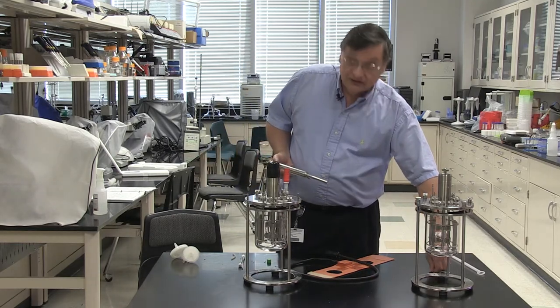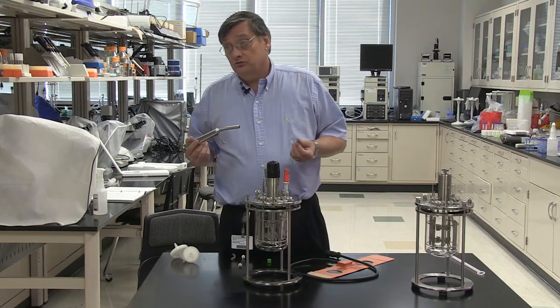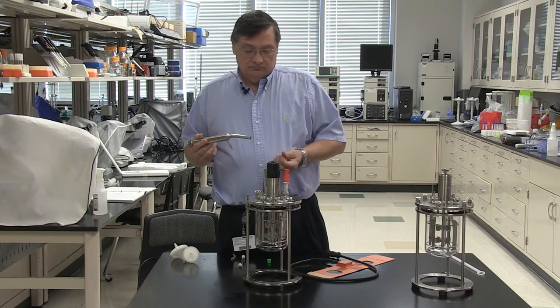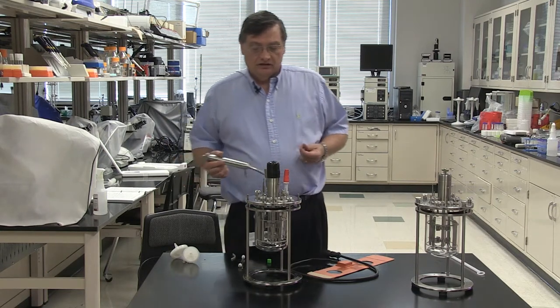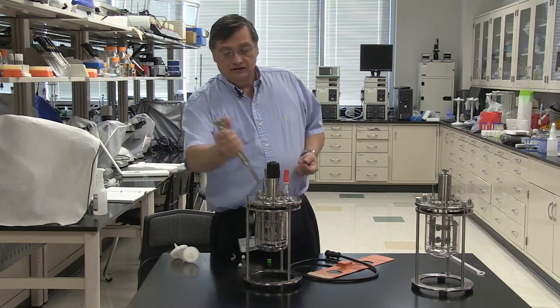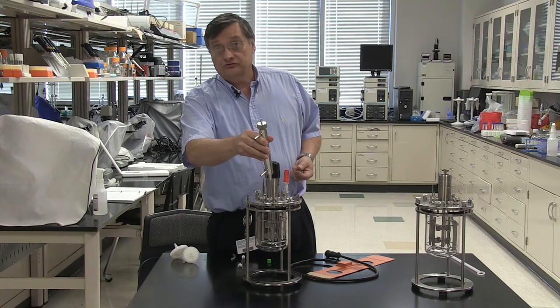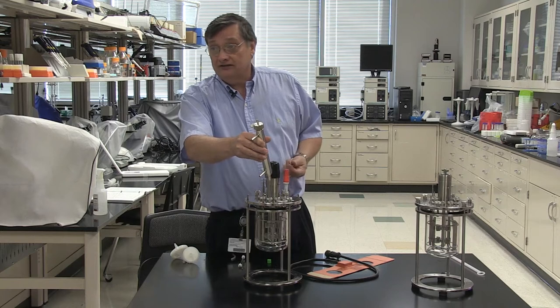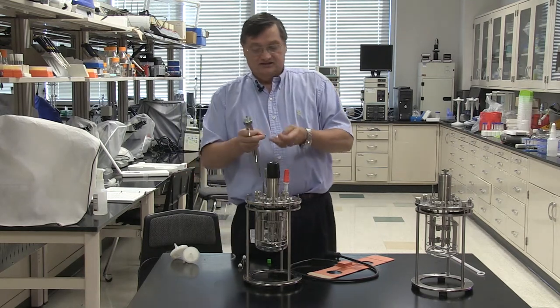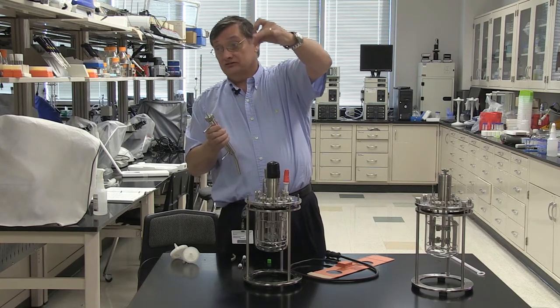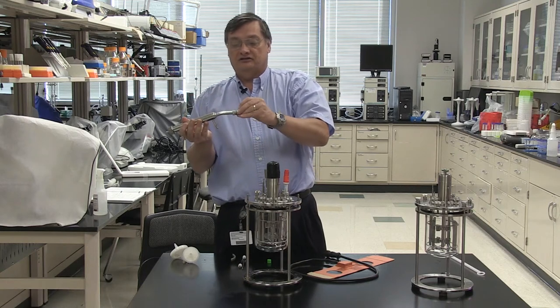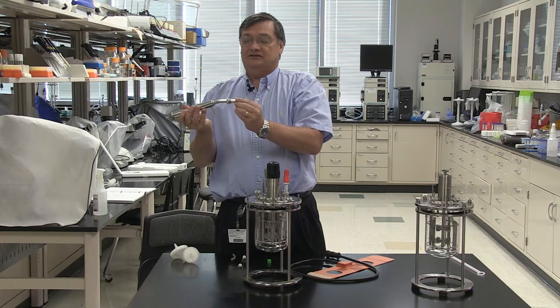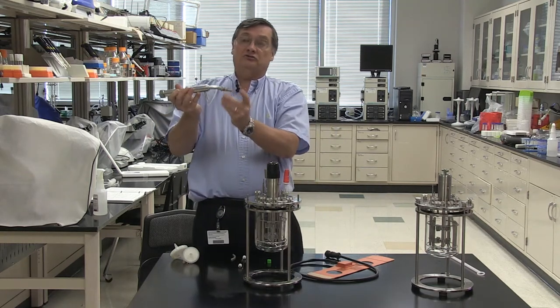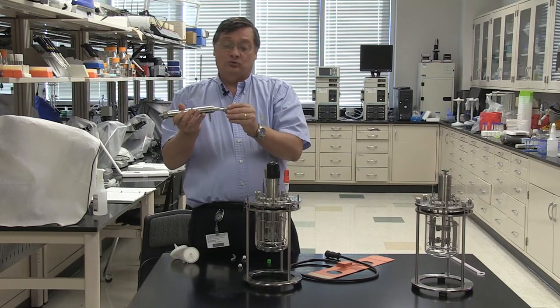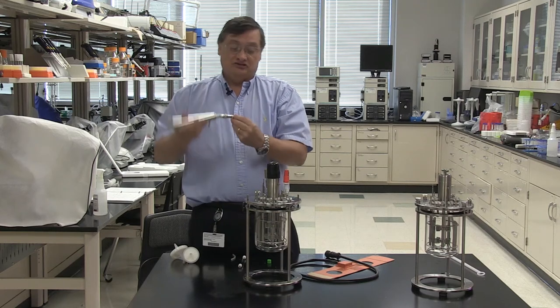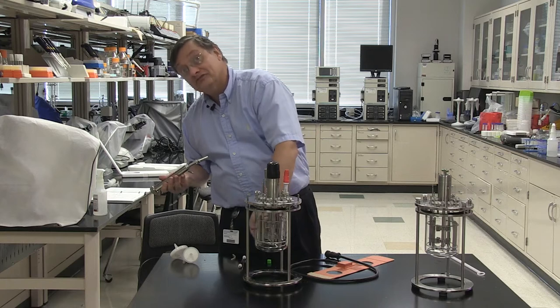Now, I guess there are a couple of ways of approaching how you attach it. Since it's metal and it's not breakable, it's okay to loosen your set screws and insert it directly through the fitting. Then you have to re-tighten the fitting. Now, the problem with doing that is at the bottom of the fitting there are two fittings, one of which is that little rubber O-ring. As you're putting it through there and you hit this little O-ring, the notion is that it would force it on to there and all would be good. In practicality, what often happens is you're trying to force it through, it actually catches it and pushes it into the vessel, and you see it just float to the bottom.